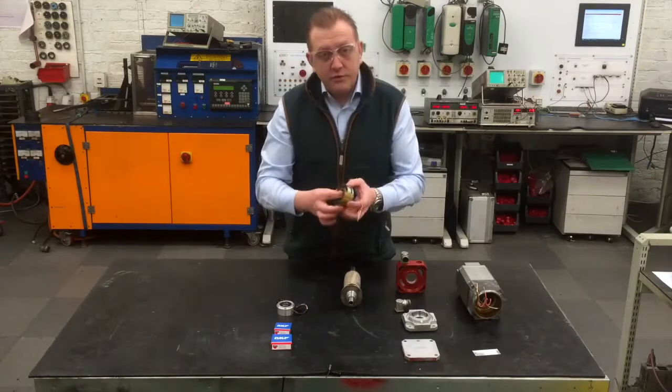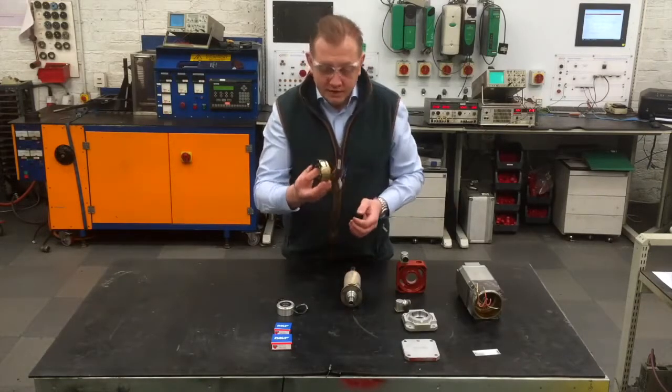The brake has been overhauled. We have dismantled the brake, cleaned everything, tested the coil, so that is good.